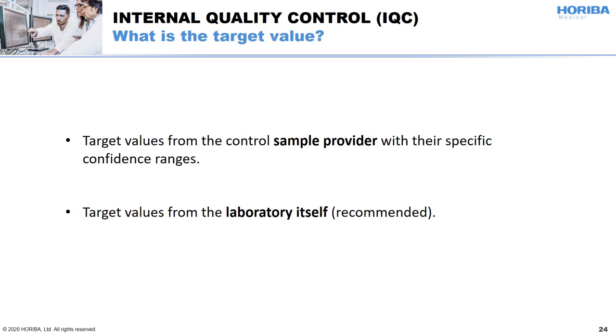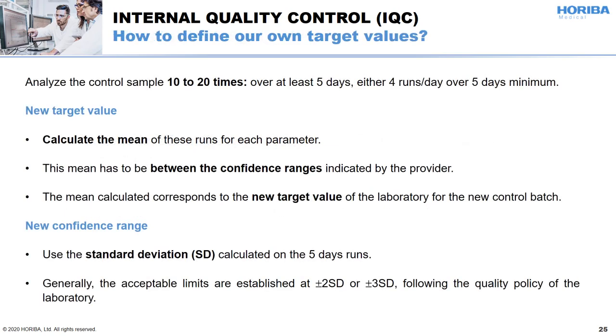What is the target value for the IQC? The target values can come from either the control sample provider or the laboratory itself. The second option is recommended because the provider's target values can have higher confidence ranges, due to the fact that they have to account for inter-instrument variations. To define its own target values, the laboratory will have to simultaneously run the new control sample batch and the current one over at least 5 days. The mean of those results will become the new target value, and the confidence range will be calculated by the SD of those runs. According to its quality policy, the laboratory can choose ±2 or ±3 SD as the confidence range.